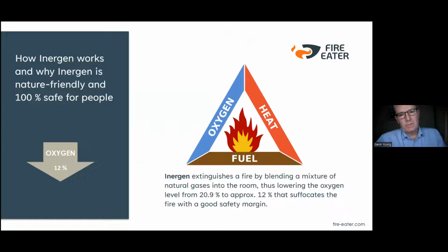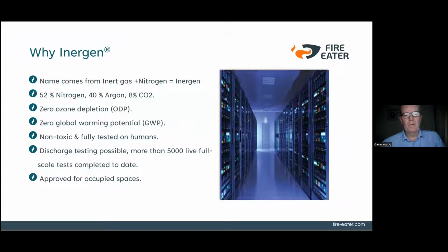So how it works is basically it reduces the oxygen level. It's at 20.9 or 21% oxygen now. When it's discharged into an area, it reduces the oxygen level to between 14 and 10%, thereby fire can't be sustained. The name Inergen comes from inert gas and nitrogen. As I said, it's got no environmental issues. It's non-toxic. It's fully tested on humans. We have done many thousands of live discharge tests, and it's proven for occupied spaces.